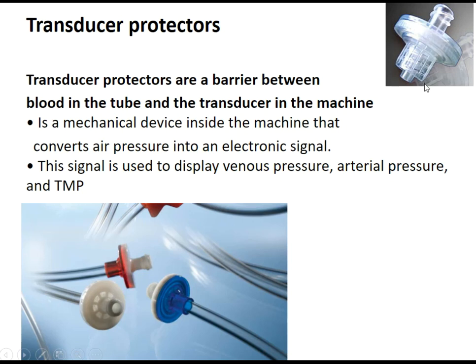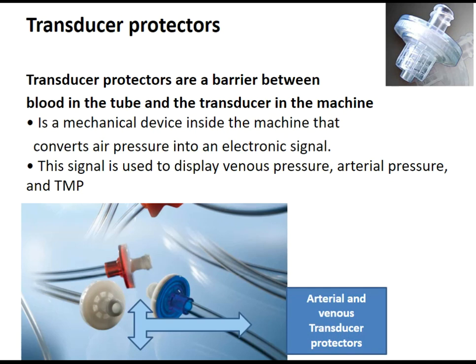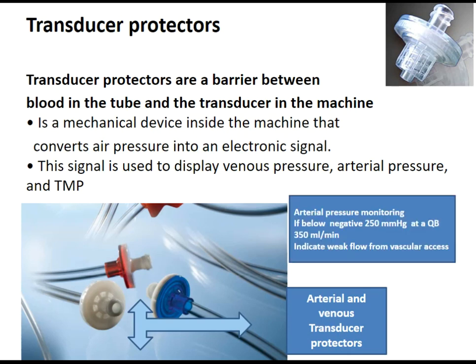The transducer protectors are a barrier between the blood in the tube and the transducer in the machine. It is a mechanical device inside the machine that converts air pressure coming from the blood circuit into an electronic signal. The signal is used to display venous pressure, arterial pressure, and the calculation of transmembrane pressure. An arterial pressure reading below negative 250 mmHg at a QB of 350 mL/min indicates weak flow from the vascular access.